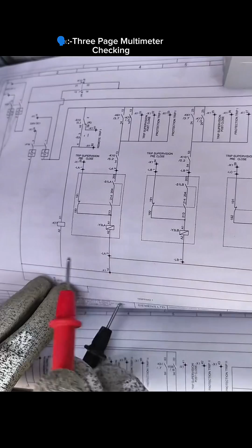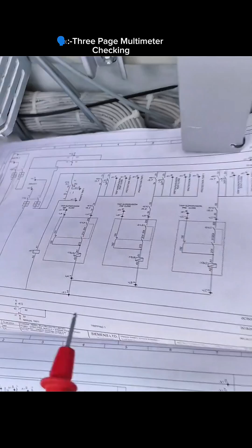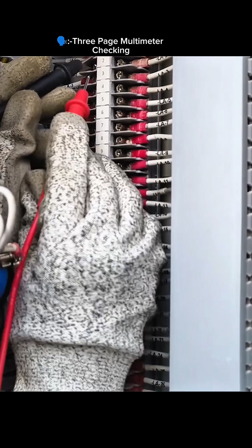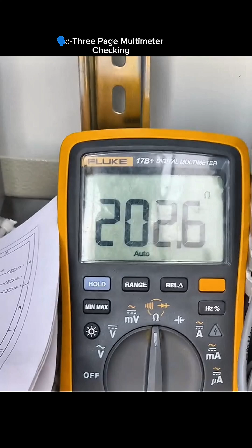Now the breaker is in open condition, so we will check the points LA3, LA1. So this is LA3, LA1. 202. 202 is okay. The minimum value is 190, the maximum value is 220. So 202 is okay. The coil is healthy.